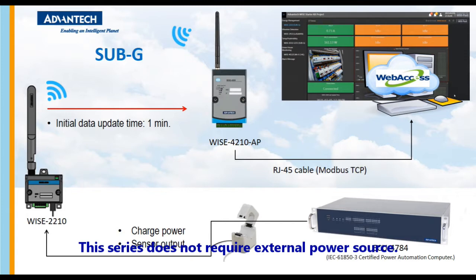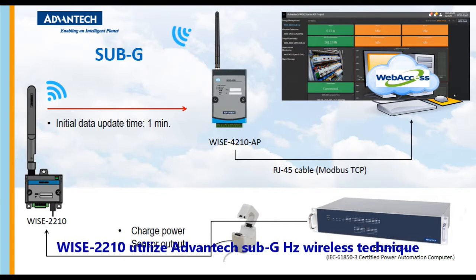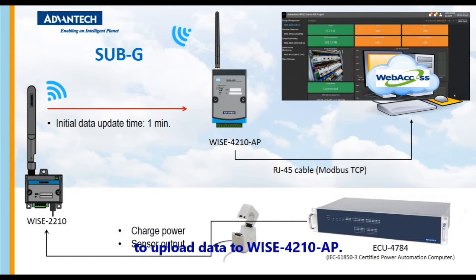This series does not require an external power source. By connecting CT modules to the three AI channels, WISE 2210 is able to monitor the current and be powered on at the same time. WISE 2210 utilizes Advantech sub-GHz wireless technique to upload data to WISE 4210AP.